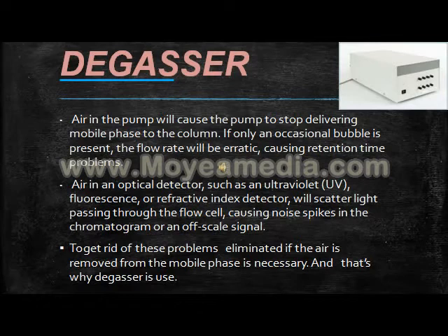If air is present in the pump, retention time problems will come. And if it is in the optical detector, the light will scatter and you will not get the proper signal; you will get noise spikes in the chromatogram or an off signal.